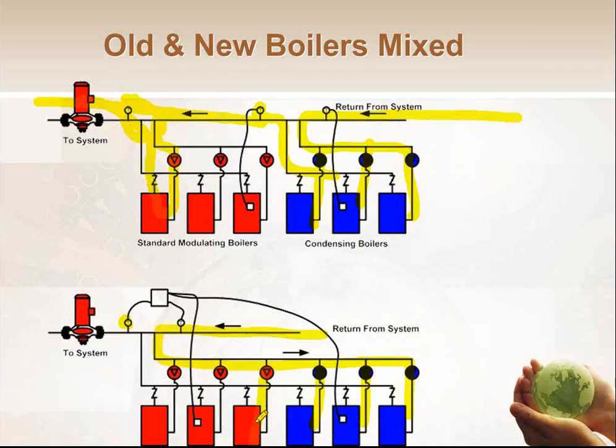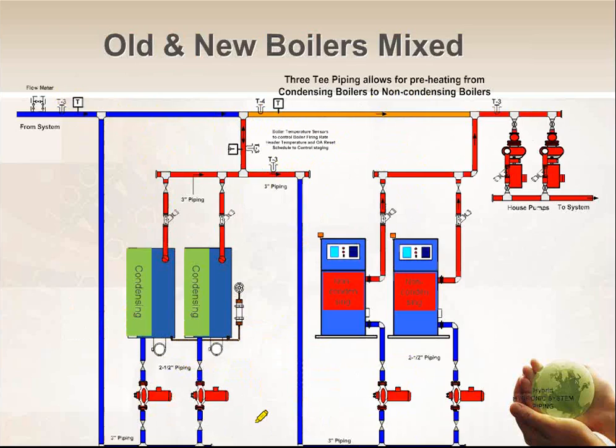Tula is asking if we have a side-by-side performance comparison summary for different boiler types. For different boiler manufacturers, probably yes, Tula, but for different types, no, because I could have a low mass that's 90% and a high mass that's 95%, or vice versa. So it's really specific to the manufacturer. It's not just a function of whether it's low mass or high mass. It's mainly a function of how big my burner is relative to the surface area of my heat exchanger. So for different manufacturers, it'll end up being a little bit different answer.